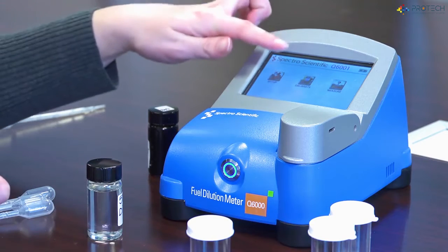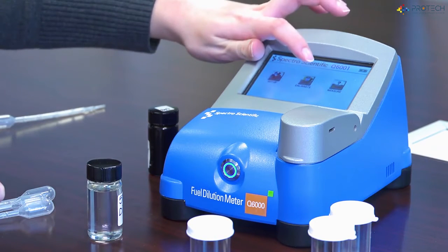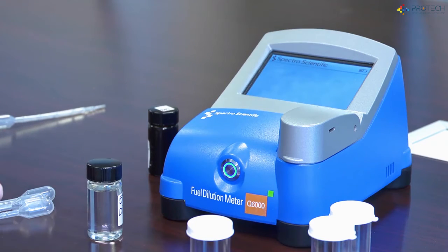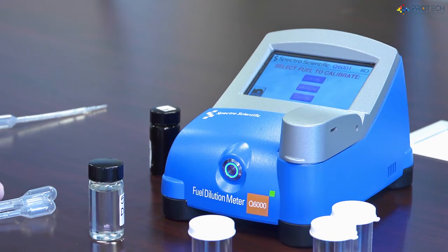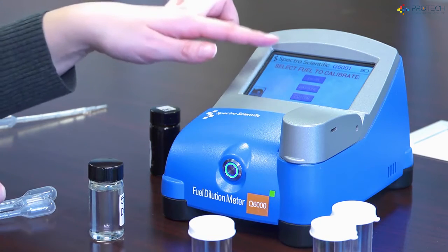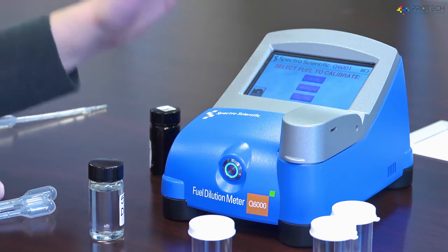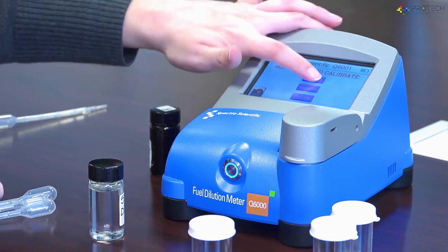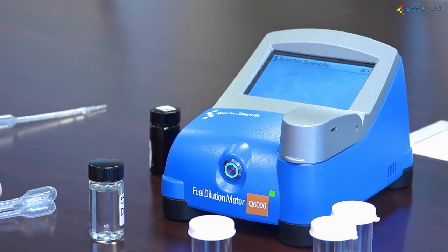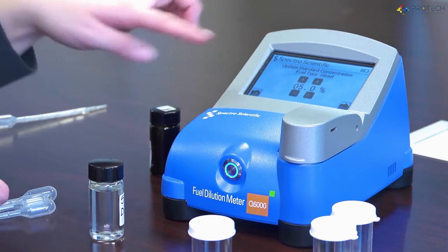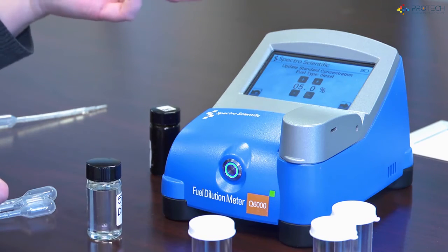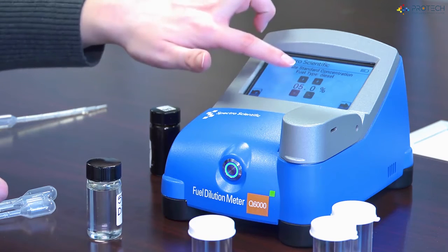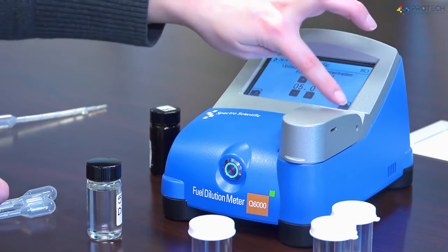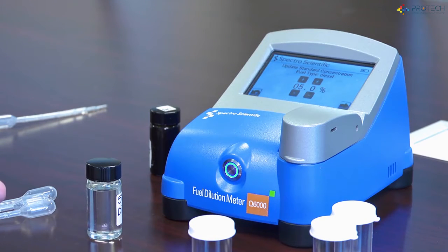While it's equilibrating, I'm going to go to the instrument and push the calibrate button. Calibrating. Select fuel type. This is a model 6001, so I have 3 calibration slots which I can choose from. I'm going to calibrate in the first slot for diesel. Calibrating. Diesel. Enter fuel concentration. Then I'm going to enter in the concentration of my standard. So my standard is 5.0%. I would use the plus and minus keys to enter in my concentration. Insert vial. Push next. Then close lid.